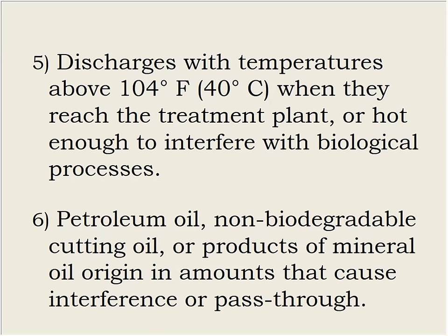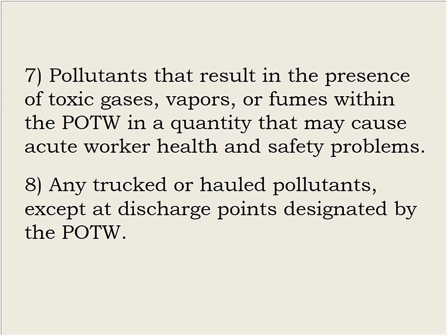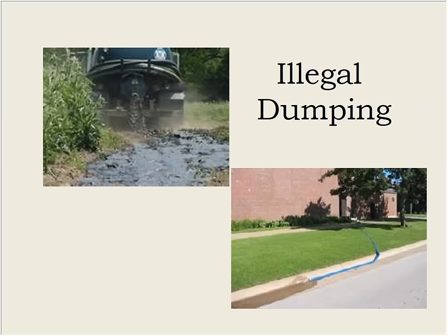Discharges with temperatures above 104 degrees Fahrenheit, 40 degrees Celsius, when it reaches the treatment plant. That's pretty much the drop-dead temperature for the organisms. That's why that's there. And the ones that will just pass through cause interference. Petroleum oil, non-biodegradable cutting oil, big organic molecules just pass on through. Anything that causes a safety issue for the operators of the collection system. And this one's for the midnight hauler: trucked or hauled pollutants except at discharge points designated by the POTW. That's not designated by the POTW, unless you're in Jersey.